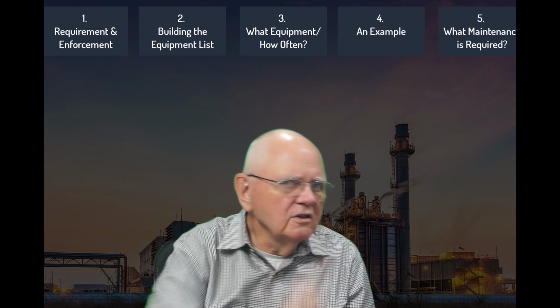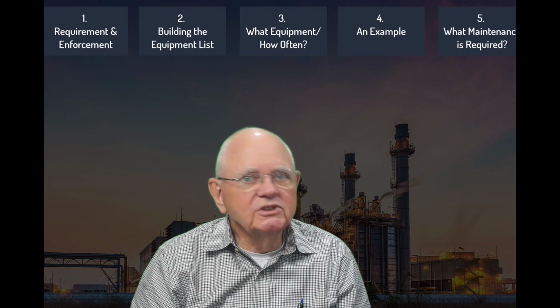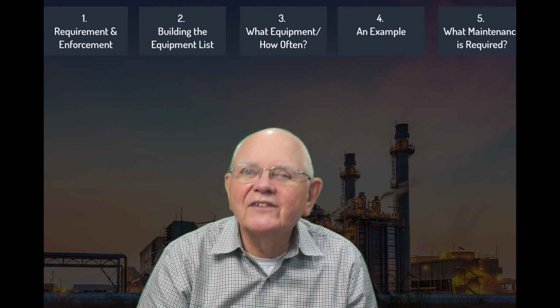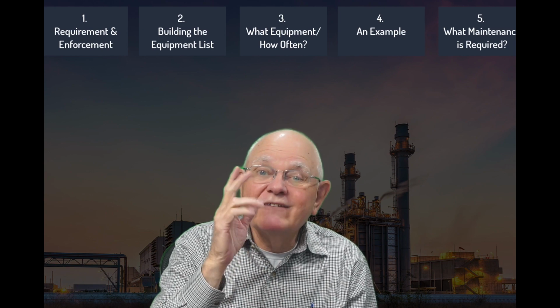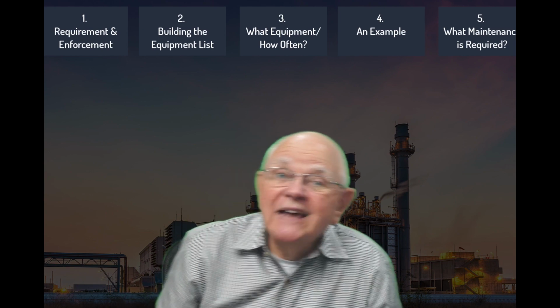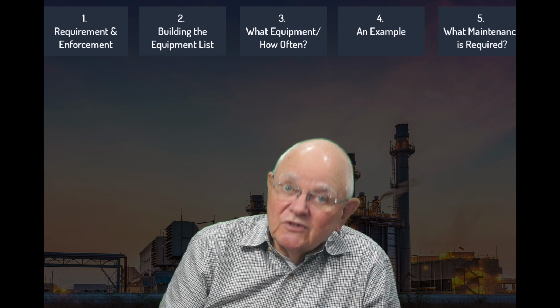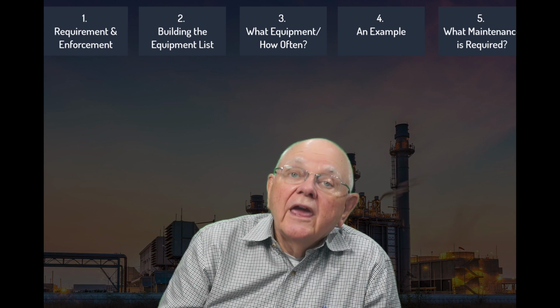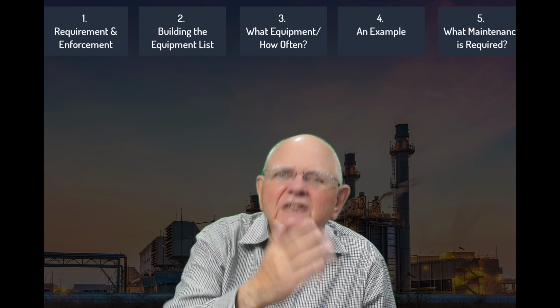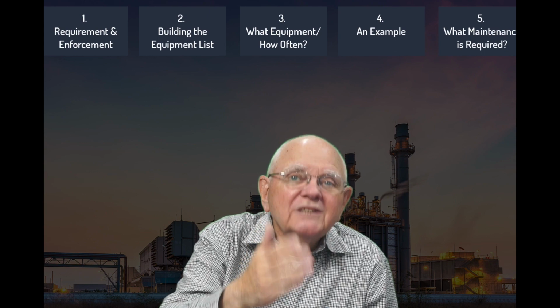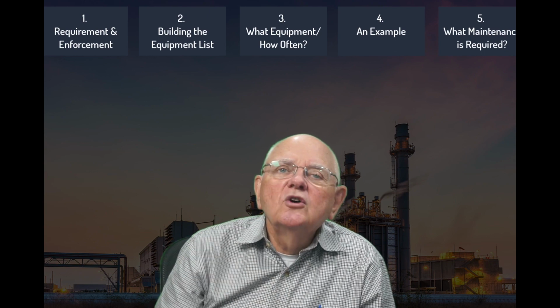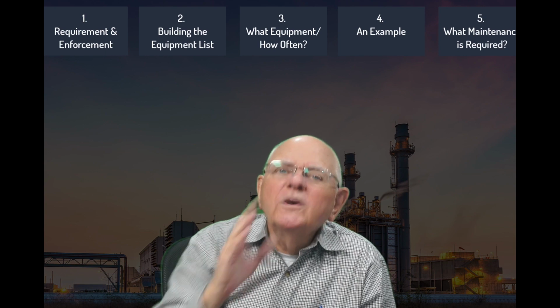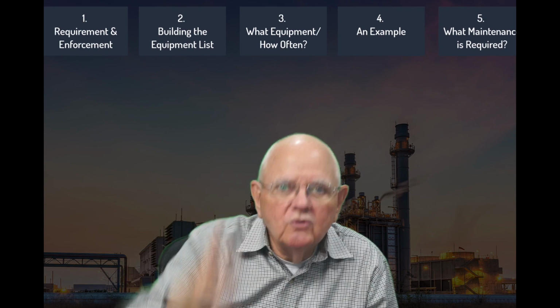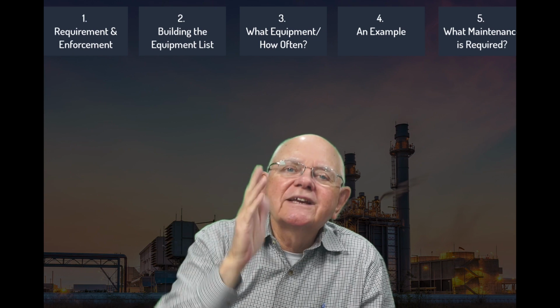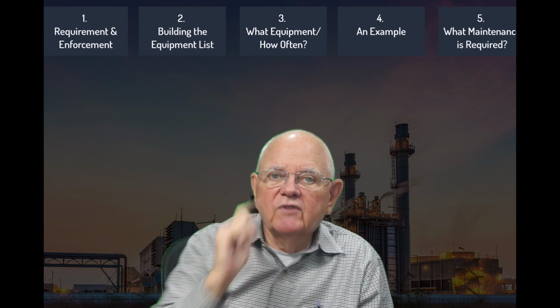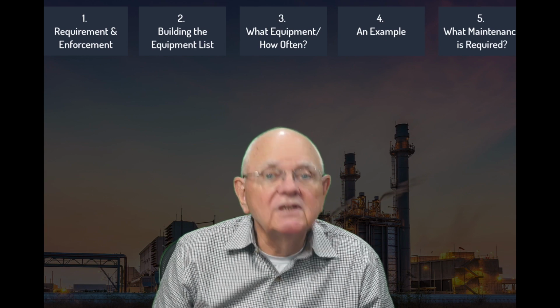However, we take a look at that panel board the transformer is supplying, and there's a ventilation fan on there in the lab area that sucks some bad gases out of the laboratory that appear once in a while. It's possible that ventilation fan could fail, and someone's health and safety could be affected in that lab area. So the company decides to assign it a criticality of 3, because if it fails, it might affect the health and safety of someone.